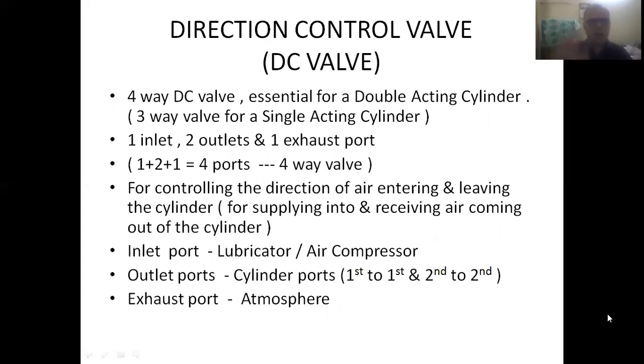So friends, we have already talked about the DC valve and its arrangements. These four-way valves are very essential for double acting cylinders, and three-way valves are very essential for single acting cylinders. As discussed in the figure, this four-way valve consists of one inlet, two outlets, and one exhaust port. So totally it is having four ports.